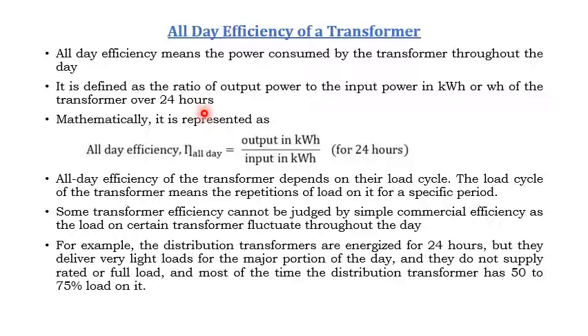This all day efficiency can be calculated in the case of a distribution transformer, because we cannot judge the efficiency of a distribution transformer at a particular instant, since at every instant the load will be changing. If the load is changing, its efficiency also changes. So in that case the all day efficiency is calculated: the ratio of output power to input power over 24 hours, in watt hour or kilowatt hour. Mathematically, all day efficiency equals output in kilowatt hour divided by input in kilowatt hour for 24 hours.